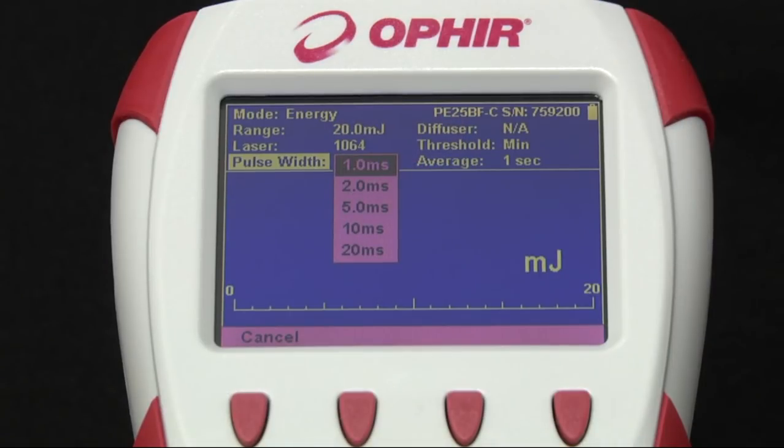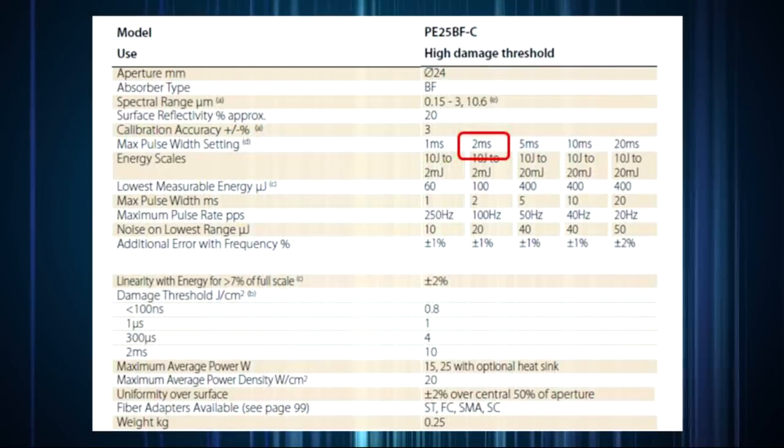This explains, it should be noted, why choosing a given maximum pulse width setting determines the maximum pulse repetition rate, as can be seen in the specifications.